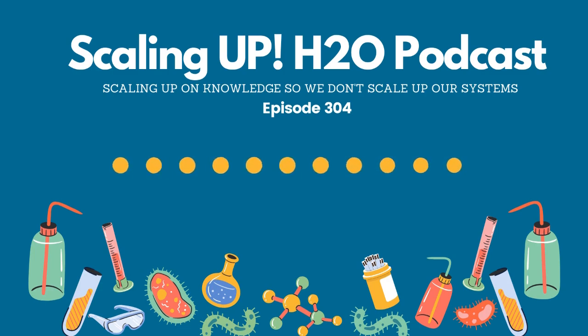Now, chances are, if you're a water treater like I am, you probably have a couple of go-to corrosion coupons that your company already has established. They already have them inventoried, and you can just simply ask for them and put them in your customer systems. So you're going to have basically two primary metals that you are going to use, but if there is a different metal in the system, that is what you need to measure. We'll get into identifying the different types of corrosion coupons as we move forward, but when the coupon is weighed and everything is said and done, it is measured in a unit called mils per year. Mils per year, quite simply put, is a 1,000th of an inch. So if you want to think of that in these terms, a heat exchanger, let's say the metal in the heat exchanger is 1/10 of an inch thick.